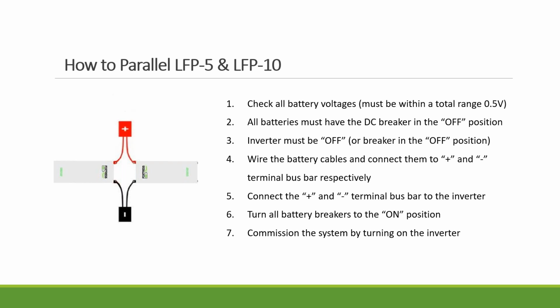Now, if you parallel the 5 and 10, there are a few important things. First of all, you use the bus bar. You make sure the cables are the same length. That way, there's no voltage or resistance difference between the batteries. And the second is that when you're doing operations, it's important to have the inverter off first and have the battery turned on first, and then turn on the inverters.